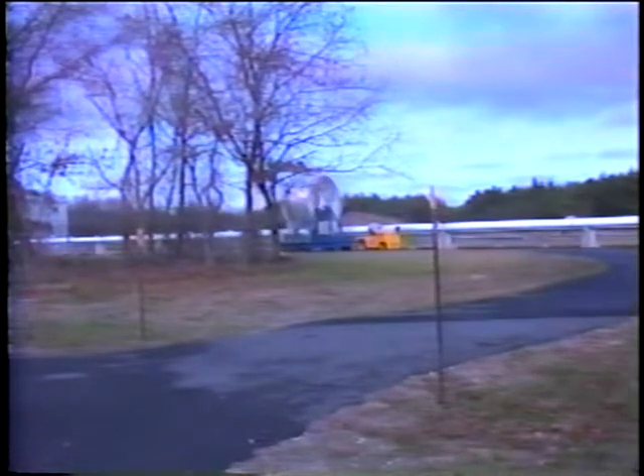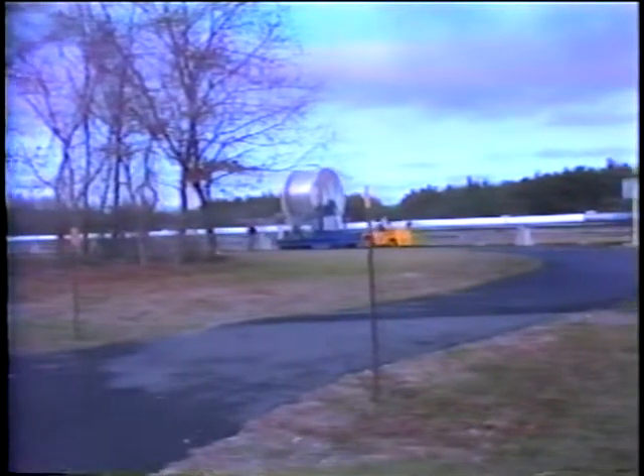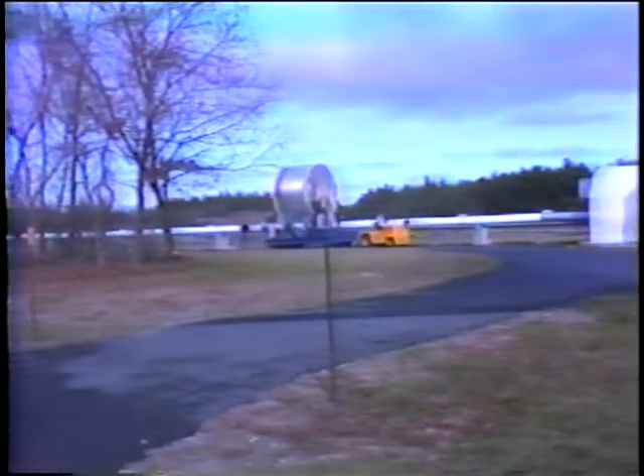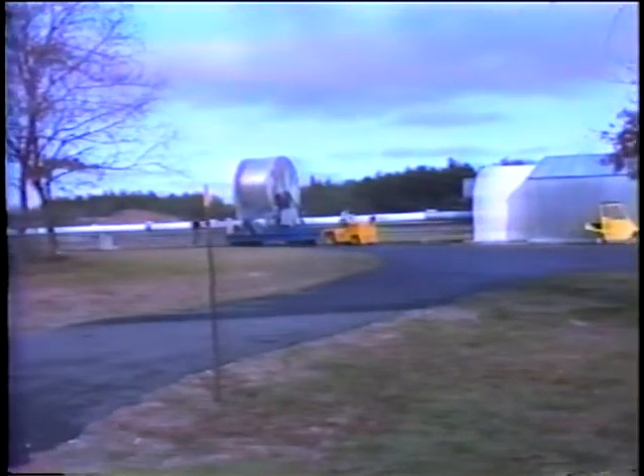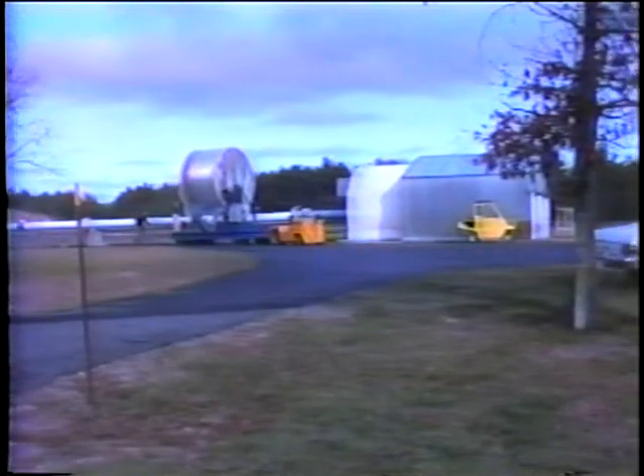The white pipe seen at the test facility is the cable enclosure. Normally, this would be underground, but at the test facility, it is placed about 3 feet above the ground for easy accessibility. This pipe itself was the subject of several years' development in order to optimize the cost and thermal performance. The outside of the pipe is at ambient temperature, but inside, the cable is operating at a temperature of only 7 degrees or so above absolute zero.